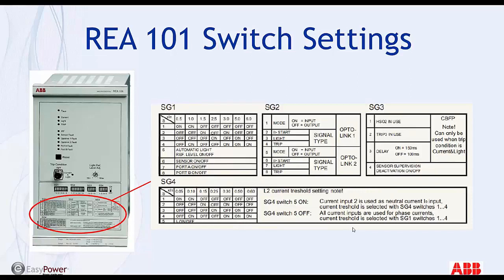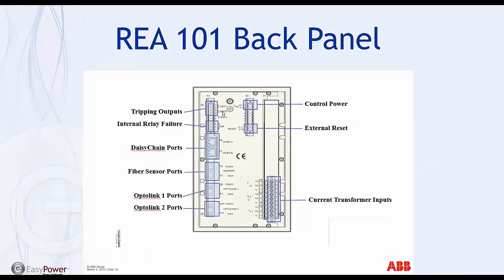So that's basically the common theme for all of these arc flash products. Here's a look at the back panel. Tripping outputs, 2 high-speed, 1 standard. A relay failure alarm. Here you can daisy chain your extension units, 2 groups of 5. You have a fiber sensor port for your loop sensor. Here are your opto links. And then you've got control power, your standard 24, 48, 120 volt DC, and also AC control power. Your external reset when you want to use a binary input to reset, and then all of your current transformer CT inputs, which can either be the 1 amp or the 5 amp nominal.